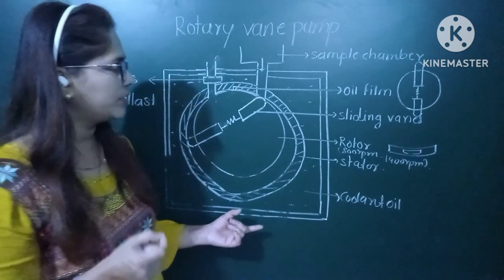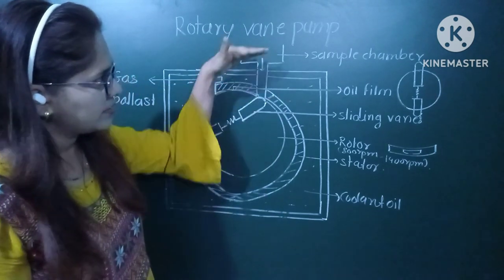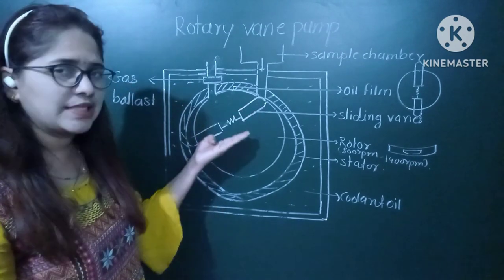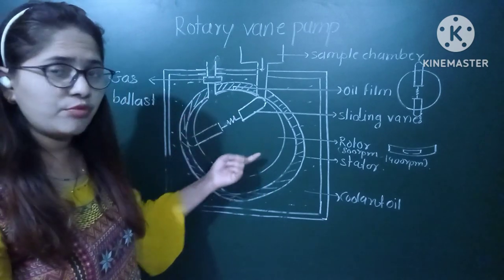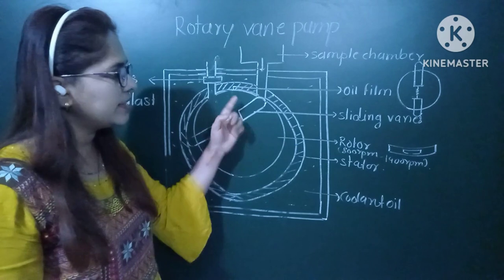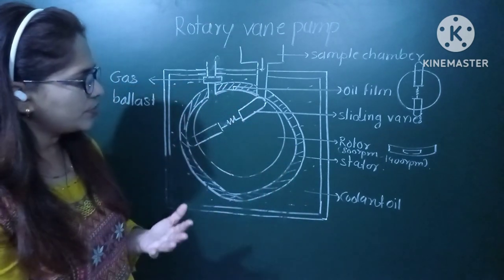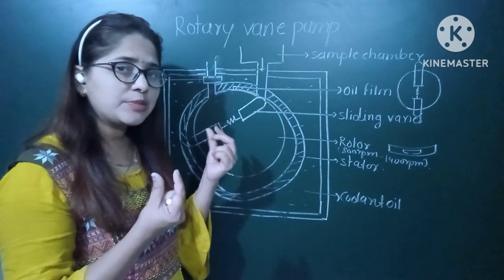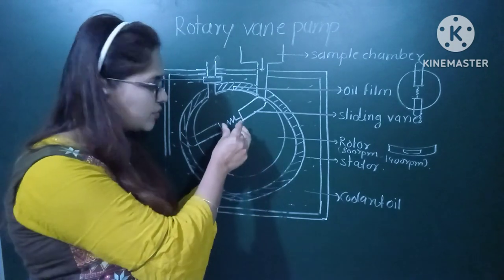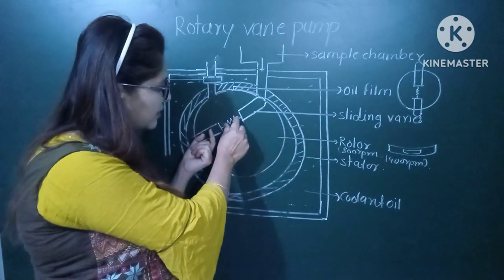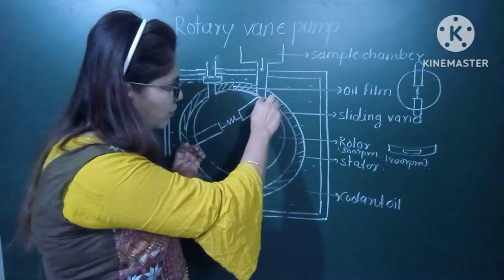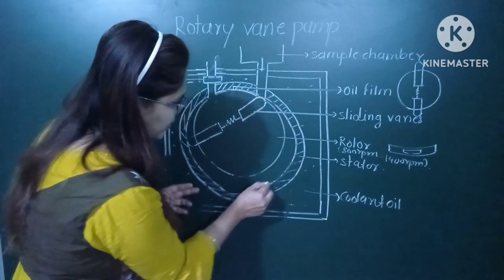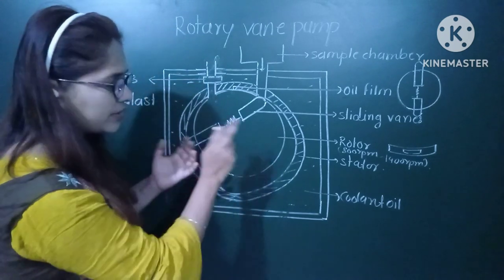Now let us see the working principle. This rotary vane pump is connected to the sample chamber. Initially, the sliding vane is at a certain position. The rotor is kept moving at 800 to 1400 RPMs and the sliding vane keeps on rotating continuously. As the vanes are connected with springs, when the distance is reduced the spring compresses, and when the distance is increased the spring expands. This maintains the contact between the sliding vane and the outer stator, so the vanes are continuously touching the stator.